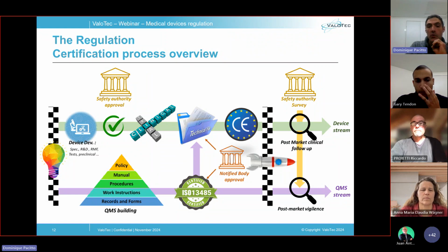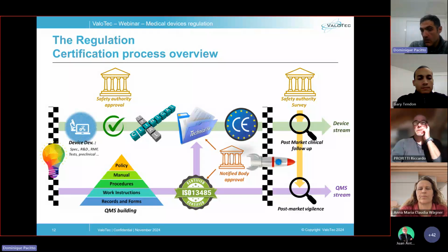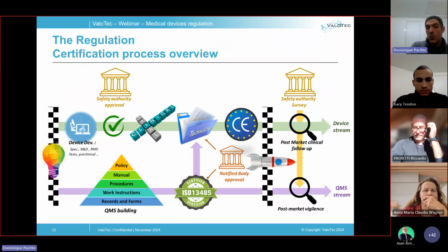Once the clinical trials are completed, all the safety evidence is gathered, and your quality management system is certified, the manufacturer sets all the data related to its product within a technical file, and this file is analyzed by the notified body, which allows the manufacturer to apply the CE mark. And once the CE mark is applied, the product can be commercialized. Keep in mind that the safety authority watches the market and the quality management system is periodically audited.